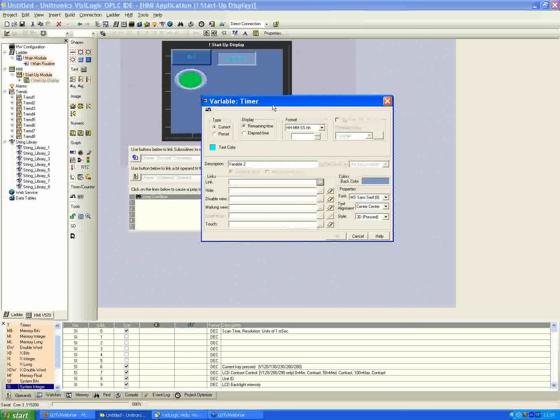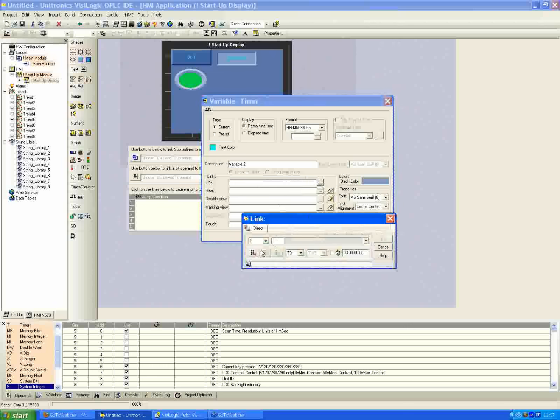You can also input the value from the HMI. First, assign a link by clicking the browse button. Using next available gives us timer zero. I'll label it 'five sec timer'. Under timer type, the dropdown shows TD, TA, or TE — which stand for timer delay, timer accumulated, and timer elapsed. We have these three different types of variable timers to work with.